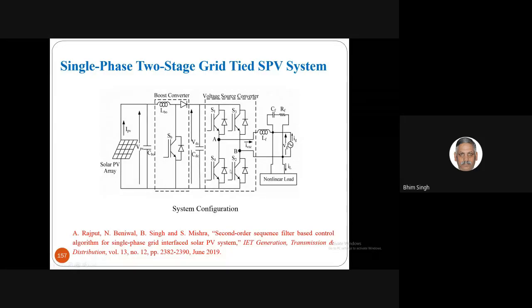The major problem is that if you can reduce the losses in the inverter by coordinating the relation between DC link voltage and this AC voltage, in some situations we are able to reduce inverter losses by around 4%. The additional losses in the boost converter were not more than 1.5 to 2%, so we are able to generate 2% more power from this solar system using a two-stage system, which works more satisfactorily and reliably compared to the single-stage system.